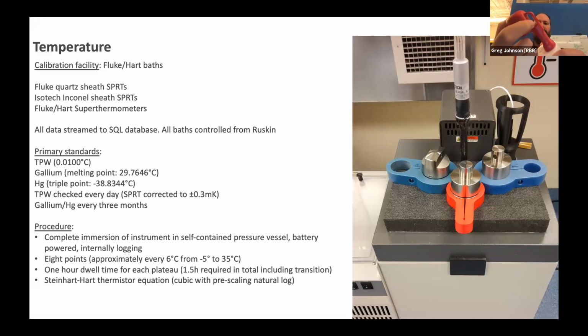This is a fast thermistor. It's a very thin one. Time constant's about 70 milliseconds. We advertise it as better than 100, but it's coming out of the factory. They're usually 70 milliseconds plus or minus about 7 or 8 milliseconds. We have a normal thermistor, a standard thermistor. Of course, I didn't bring one today.